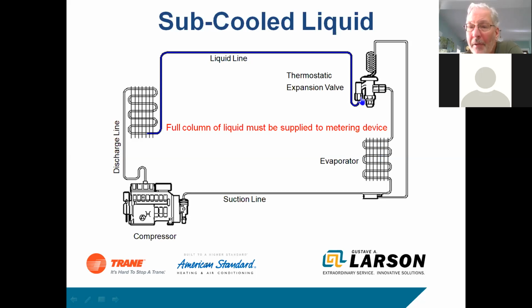We could have debris in the valve. I remember a couple of years ago, we had, I can't remember what the oil additive was that we had to put in there. The valves were plugging up, and then what would happen is it wouldn't meter properly, and we'd see 40, 50 degrees of superheat. That's a bad valve. Before you condemn the valve, make sure you've got a good charge. If the charge is right, and we're still getting 40, 50 degrees of superheat out of this, and the return air is normal, the blower is working, the filters are clean, everything checks out, then you probably have a bad valve at that point, okay?